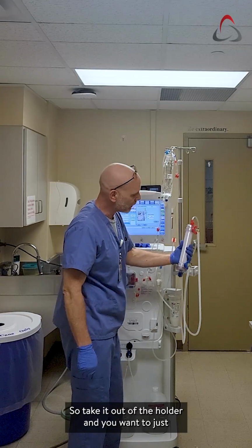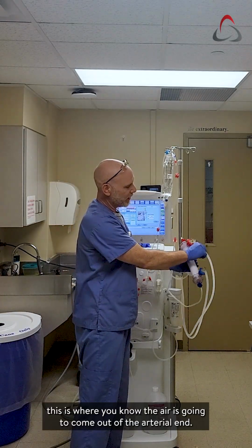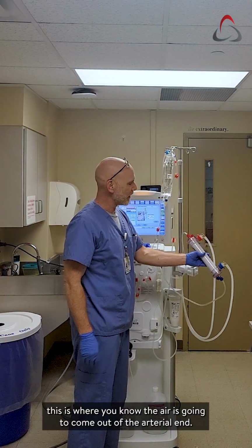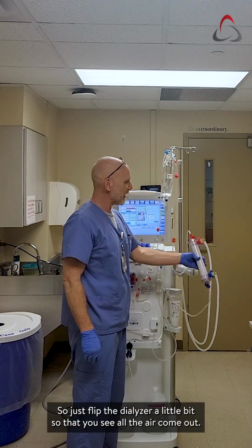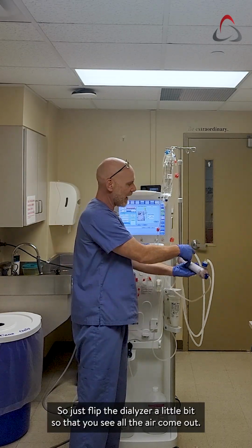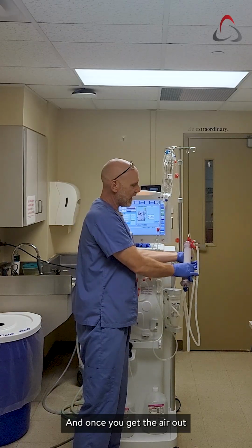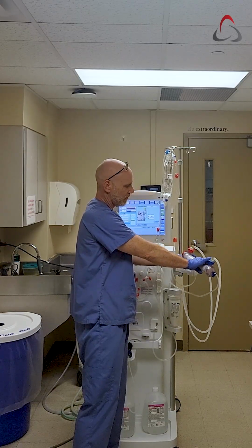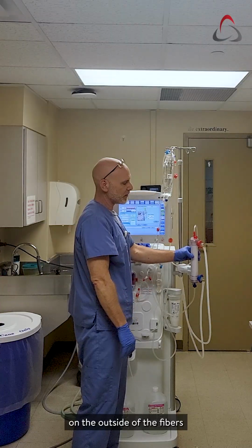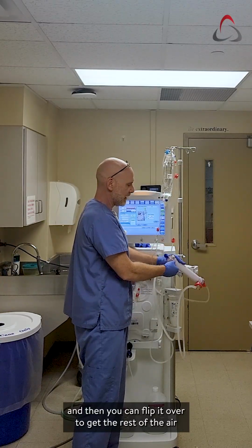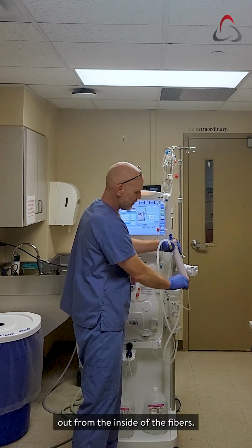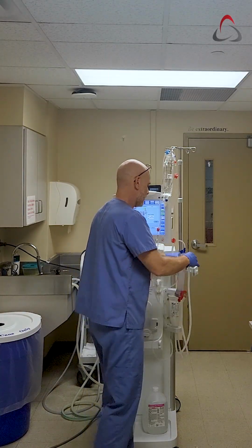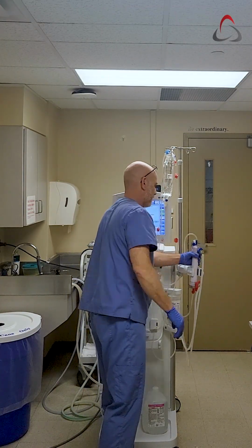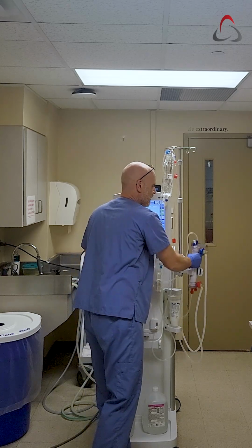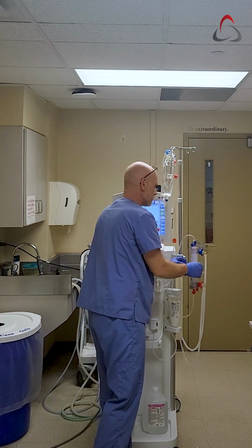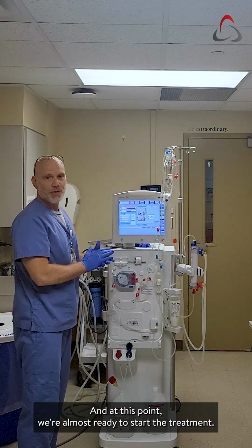So take it out of the holder, and this is where the air is going to come out of the arterial end. So just flip the dialyzer a little bit so that you see all the air come out. And then once you get the air out on the outside of the fibers, you can flip it over to get the rest of the air out from the inside of the fibers. And at this point, we're almost ready to start the treatment.